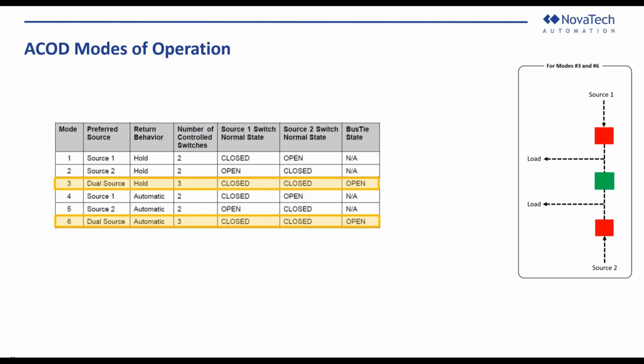Here we have modes 3 and 6 highlighted. These are both dual source, and they do utilize a bus tie. You can see that the one line diagram has changed there. This is similar to what Ray was discussing in his section about the tiebreaker control. So since that's already been discussed, we'll go back and focus on the other modes: 1, 2, 4, and 5.